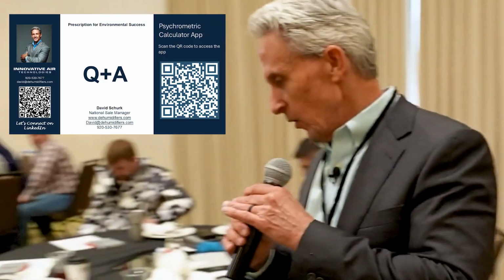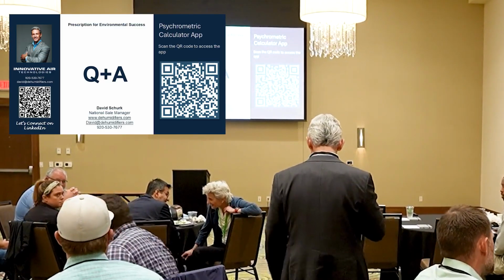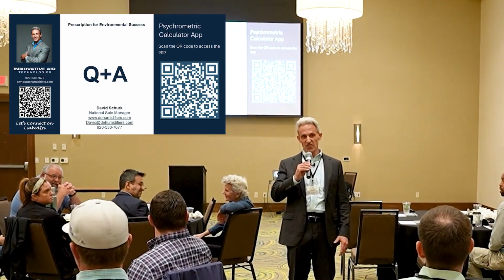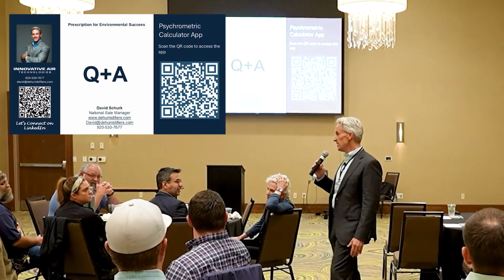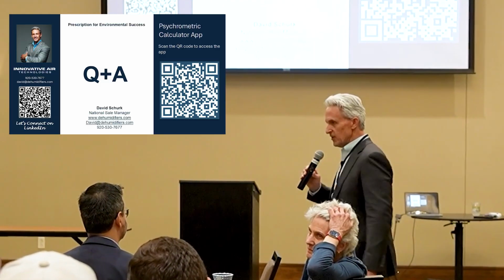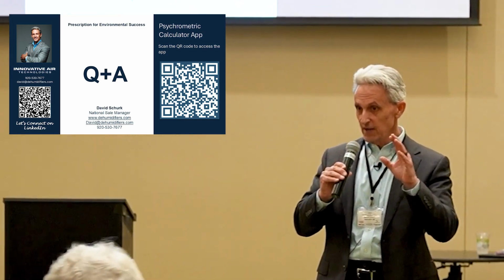That's Brian. Yeah, Brian made a really good point. Everybody looks at the wheel and they go, a wheel's a wheel's a wheel, right? It's not. A desiccant dehumidification wheel is not an energy recovery wheel, and an energy recovery wheel is not a dehumidifier, period. If you're assuming they are, confusing one with the other, that may be the problem. Maybe we need to talk about that. Because an ERV will not dehumidify the air. You need a dehumidifier to do it. It will exchange energy. That's it, right?